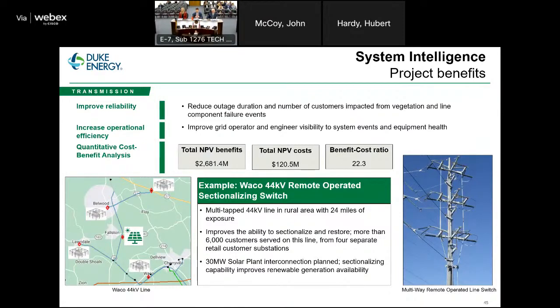The advantage of deploying a remote multi-way sectionalizing switch on this line is that if we have a problem, our grid operators can sense that, reroute power, and isolate the faulted portion in a much smaller segment than the entire circuit being operated from the substation breaker. So we can isolate the problem to a smaller area, and the rest of the customers, as well as the generation resource, can be restored and provide its benefit back onto the grid.